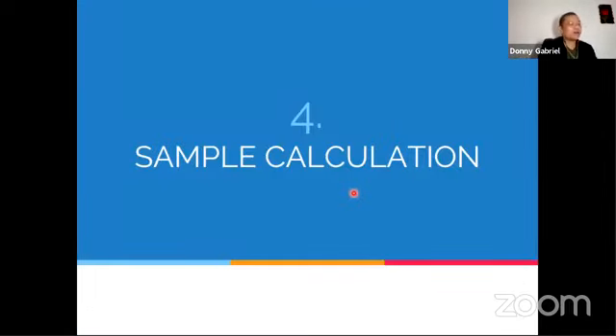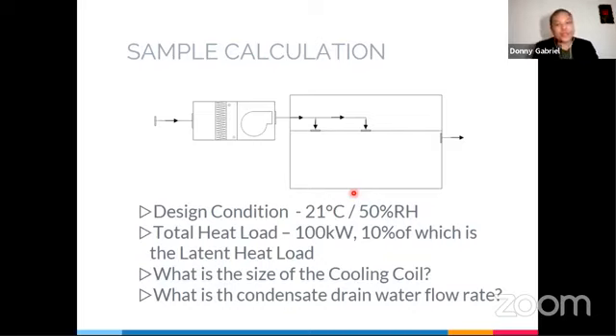Okay, so we will have our sample calculation. Let's say in our sample calculation, we want to design a room. Regardless of the size, the room is designed at 21 degrees Celsius, 50% RH. When you design a room, we estimate that the total heat load is 100 kilowatt. At 100 kilowatt, what is the size that we need for the cooling coil? How big is the cooling coil that we need? And what is the condensate drain water flow rate? This cooling coil will, in Tagalog, magpapawis, or will have a condensate. How much water will come out from this equipment, from this unit?